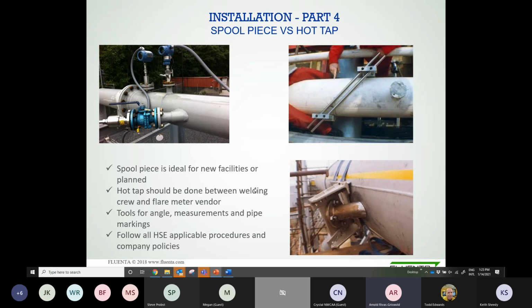The next consideration will be the decision to buy a spool piece or do a hot tap installation. Many of these ultrasonic meters use the transit time of the signal as the main principle. This is not the best picture, but we'll see it later in another slide. We send signals back and forth between the two sensors, and we measure the transit time, which is later correlated to velocity. But then you need a certain angle in relation to the pipe. Typically it's around 45 degrees, so you can get the best signal, a signal going with the flow and a signal going against the flow, and that differential will help you calculate the velocity.